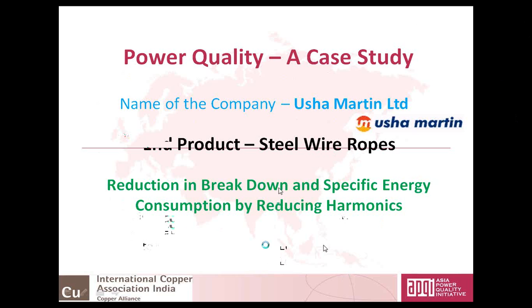Then we contacted many experts and our engineers. We discussed, and it was concluded that the quality of power may not be correct, so we should check the quality of power in the plant. So we went for a harmonic study, which was done by a party at Bangalore, Ancon actually. After they studied, they found the level of harmonics as you see in the table. The harmonic level and the voltage and current distortion levels you can also see. In the remarks, if you take the example of TRF transformer number 7, we were having a level of 37% in current distortion.